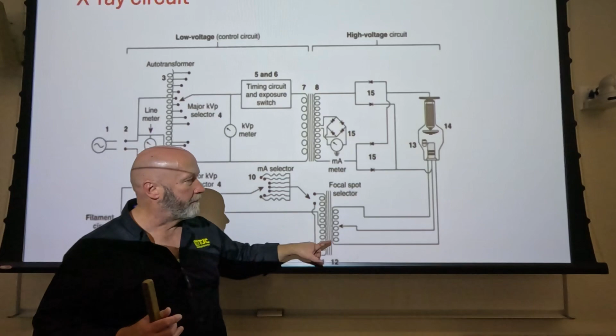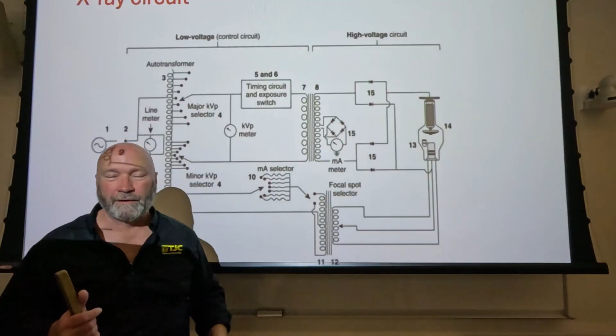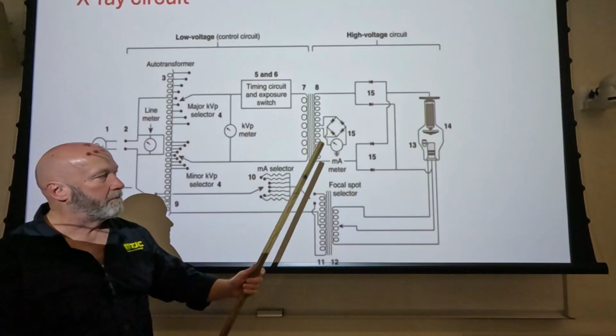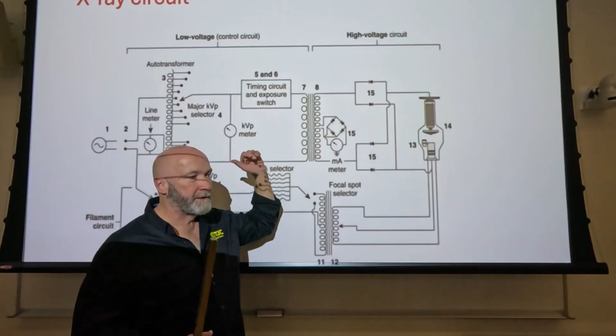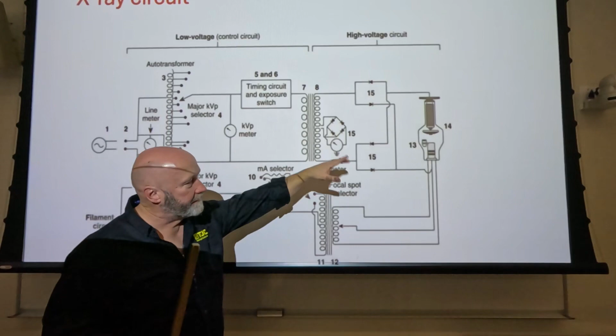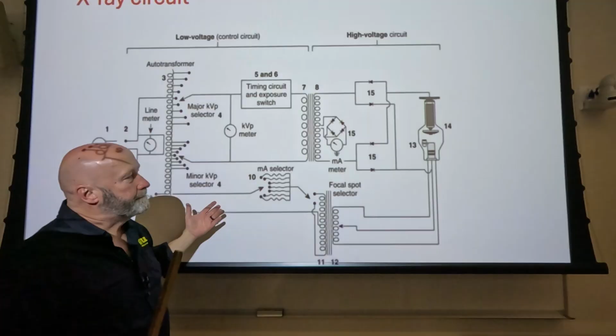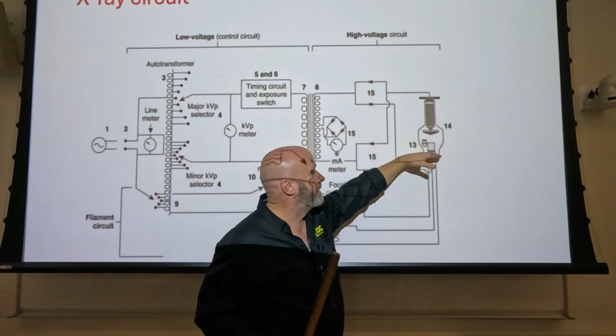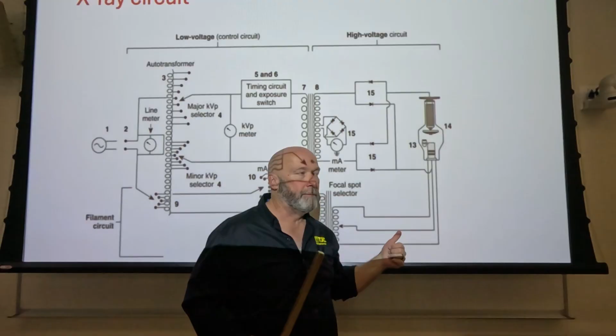We don't want high voltage until we hit it with a kilovoltage, so we're going to send it out of the MA selector into a step-down transformer. And what that's going to do is step down our voltage so that we're at maybe 25 volts. So that once we activate this during the prep stage, all we do is get a heating of the filament, and we don't send electrons across the tube until we hit the second stage, push the button all the way down, or hit your exposure button, and then the electrons jump across. So as we increase kVp, we increase the potential energy between the cathode and the anode in the X-ray tube, so that when we hit our exposure button, the higher kVp sends those electrons across the tube faster, carrying more kinetic energy.